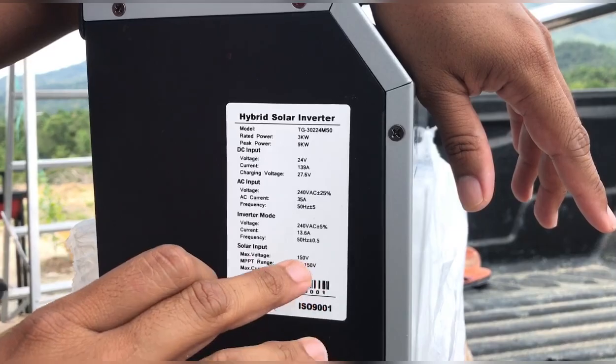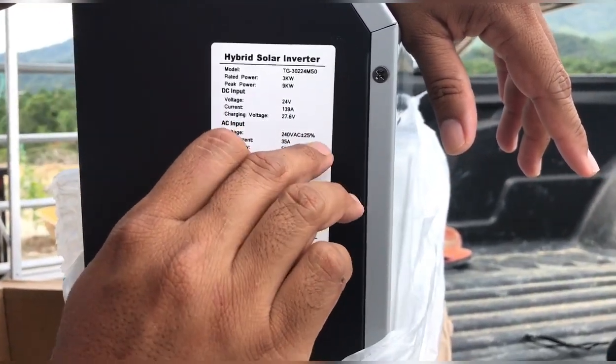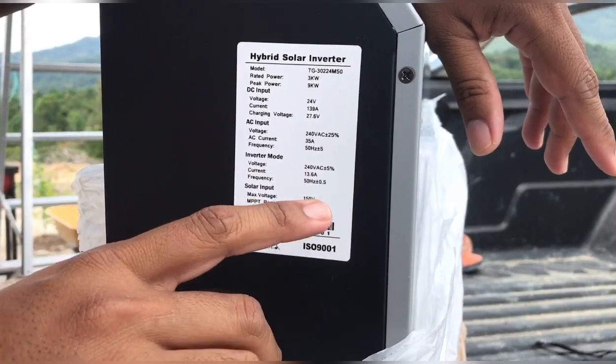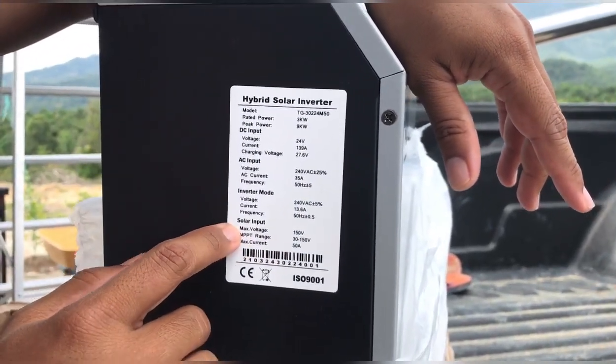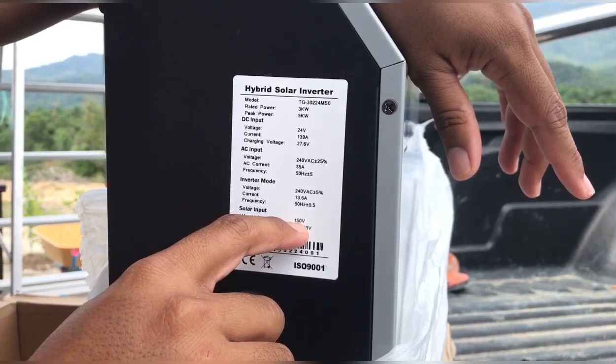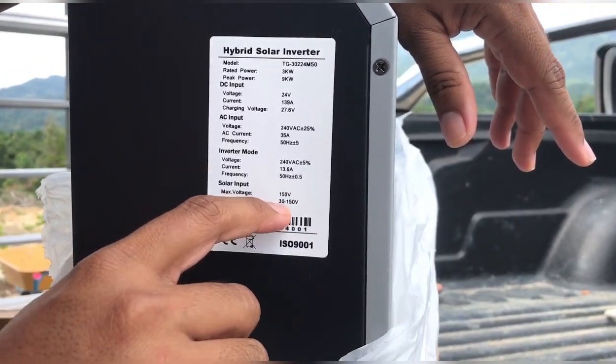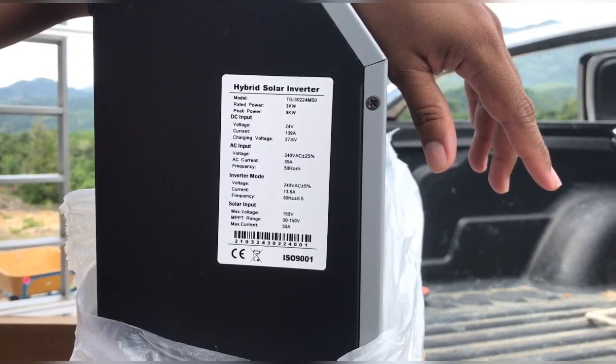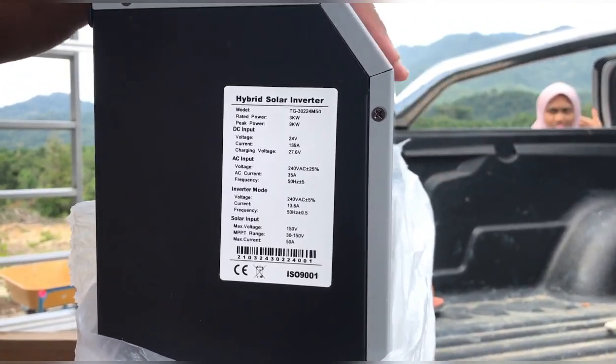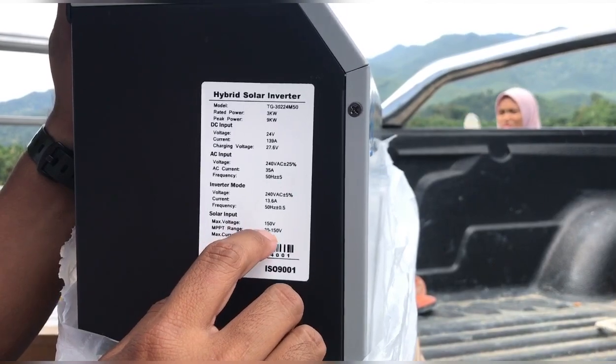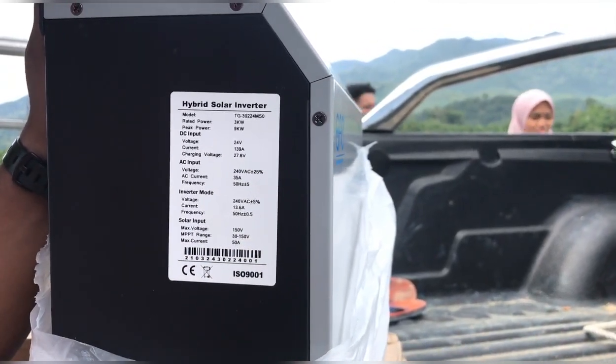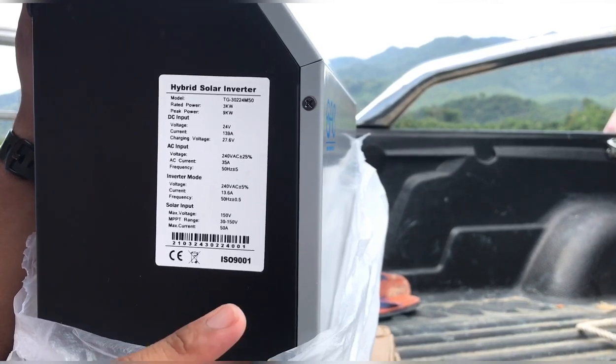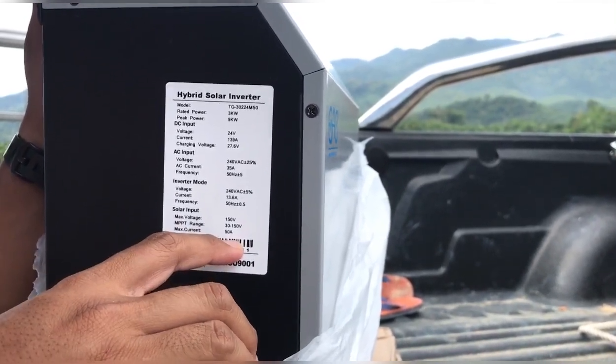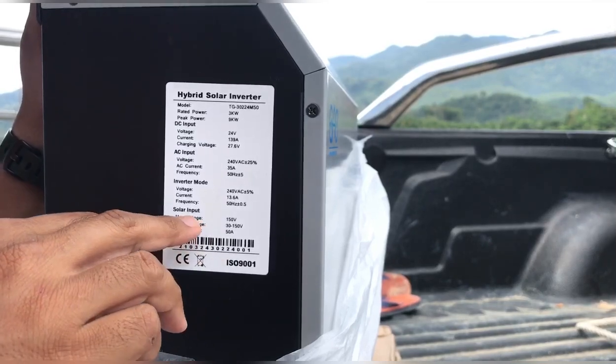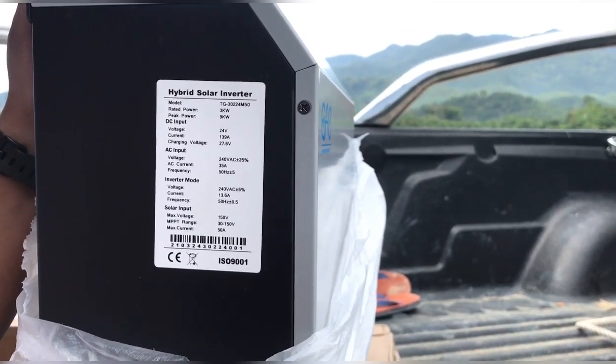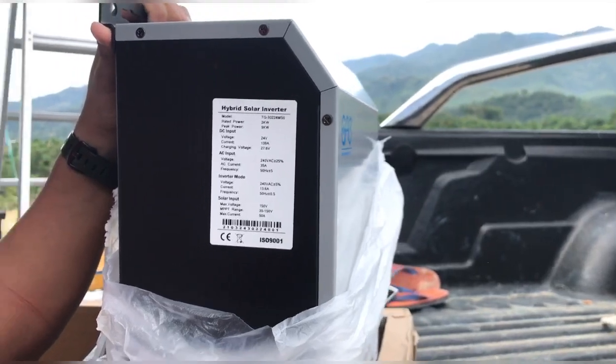Inverter mode also 240. Sorry, the AC input, it can be grid or it can be generator. The output will be 240 volt. And quite important, that's the solar input. You must see here, 150 volt. It means that the MPPT range is from 30 to 150. Our panel is around 49.4 volt. So we can use up to 3 panels, but for this installation, we only use 2, and the max current is 50 amp. So 50 amp, if you times 24 volt, you can get around 1,200 watts.